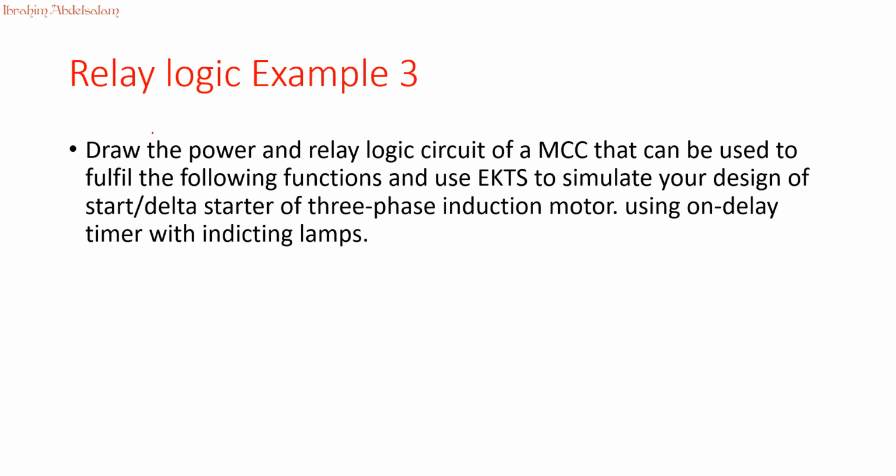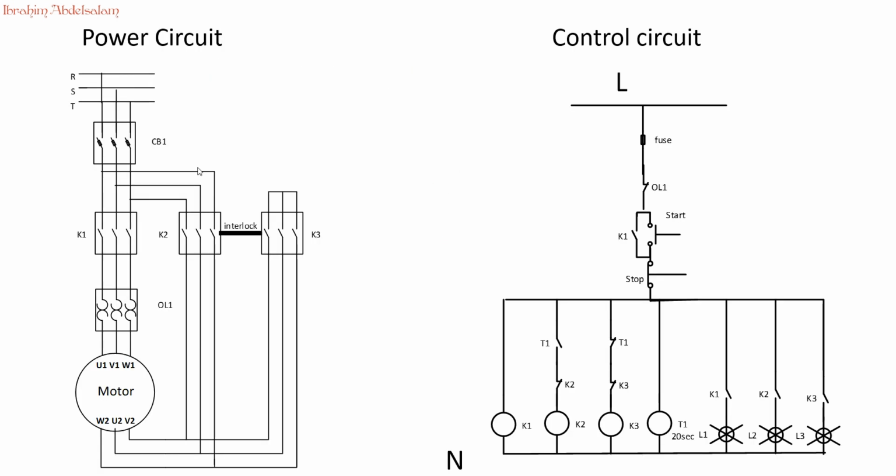Okay, relay logic example 3. Draw the power and relay logic circuit of a motor control center that can be used to fulfill the following functions, and use EKTS to simulate your design of a star delta starter of a three-phase induction motor using an on delay timer with indication lamps. Okay, let's see our design.